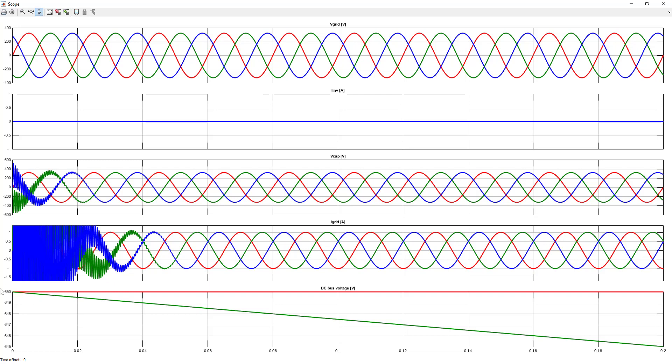What you see here is that your DC bus starts from a value. In your file, it says 600 volts DC, but I've changed it to 650. It starts from 650 volts DC, and then it starts to decrease. That's because there is no power exchange with the grid, and there is a power loss because of this resistance that is in parallel to the bus capacitor.